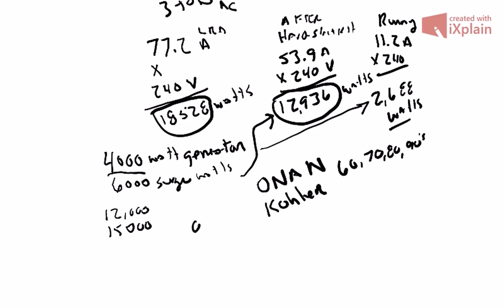Now I'm going to give you a model number of one that would work, but you would be pushing it. And that's an Onan 5CCK. So that stands for 5,000 running watts. Now these generators were so well designed that a lot of them often have a 2.5 to 3 times surge rating. So as an example, if we just took a round numbers of 5,000 times 3, we would have a 15,000 surge.